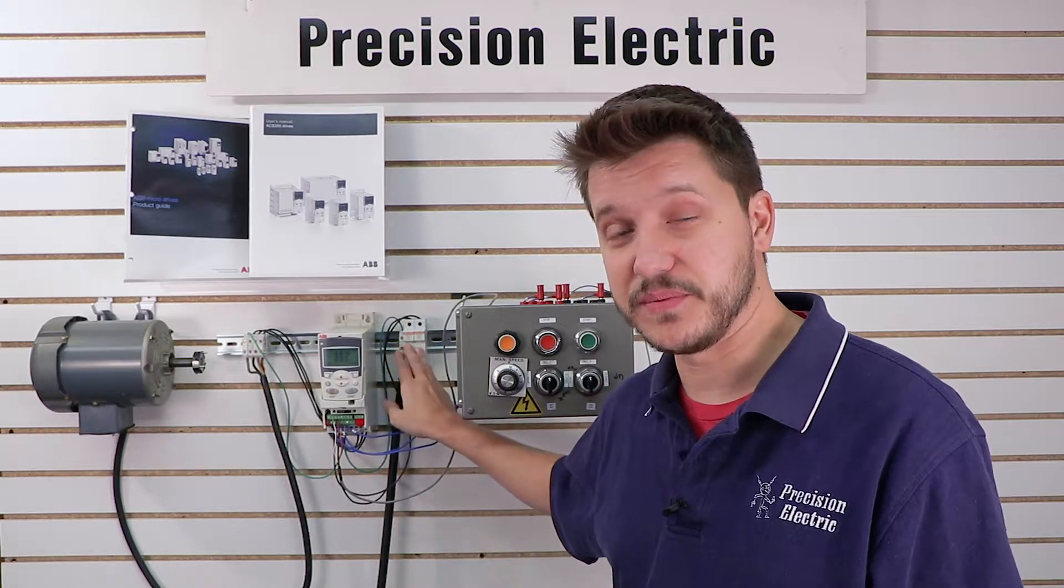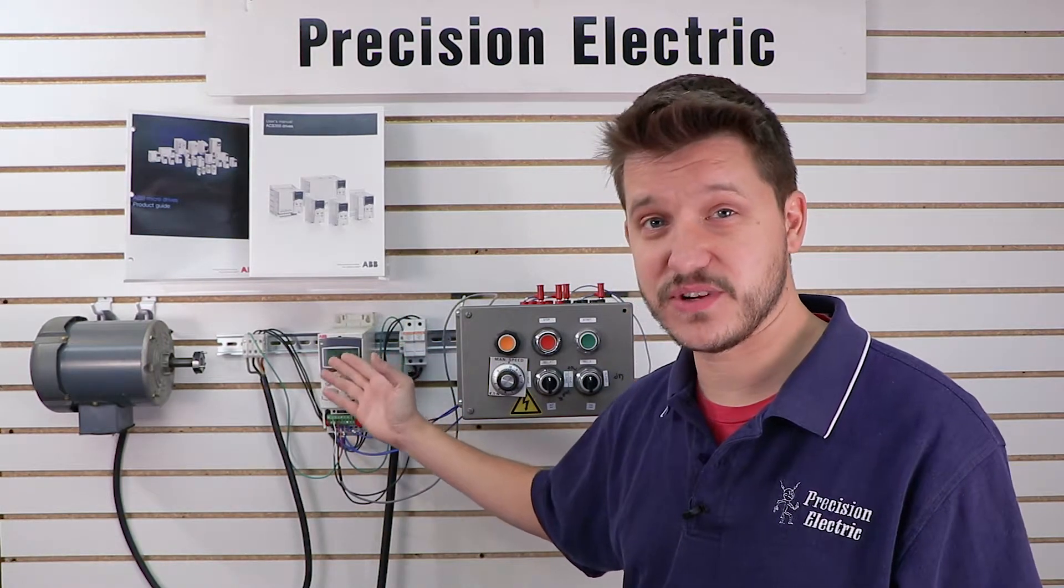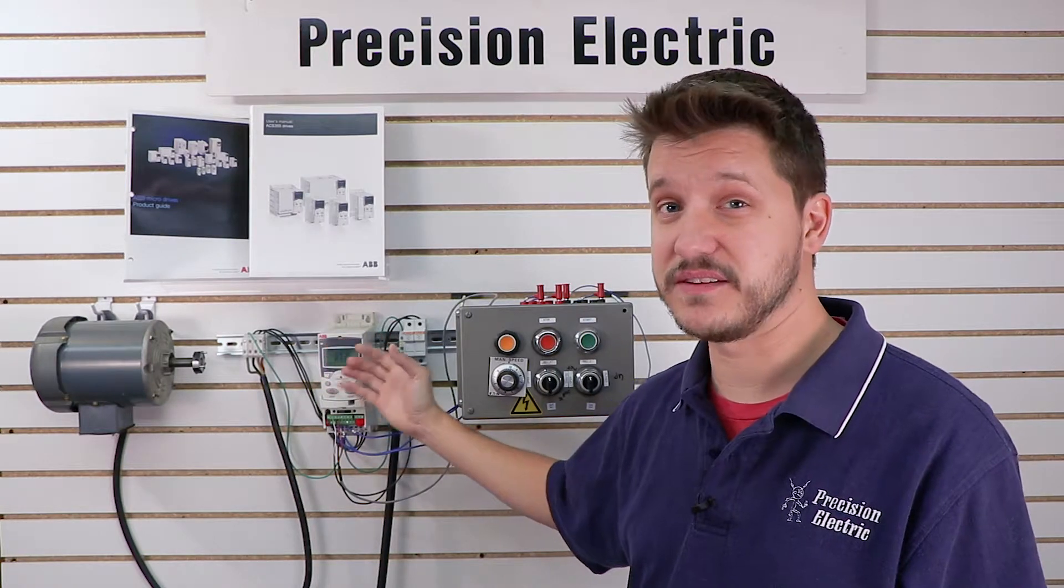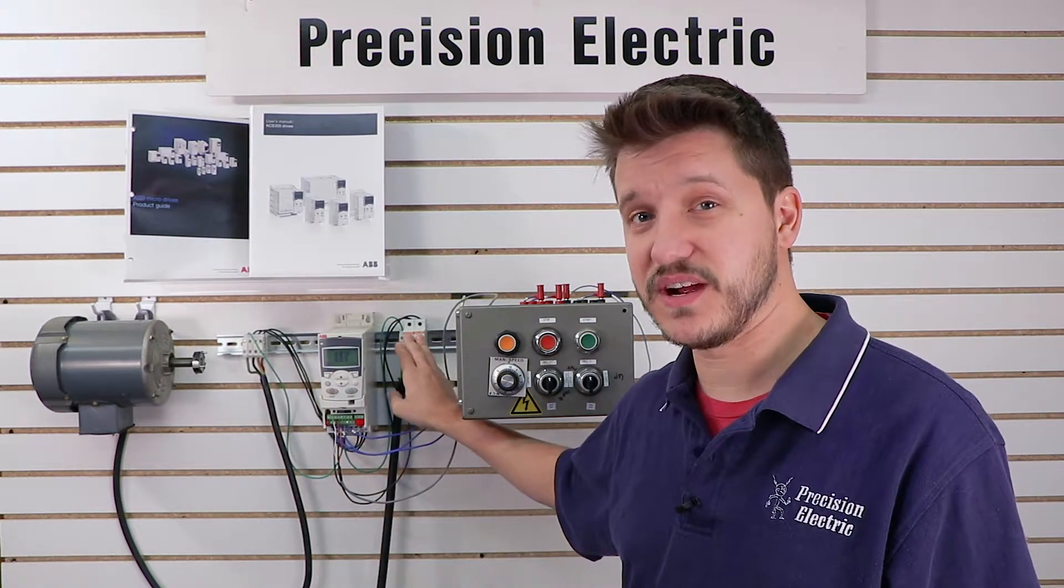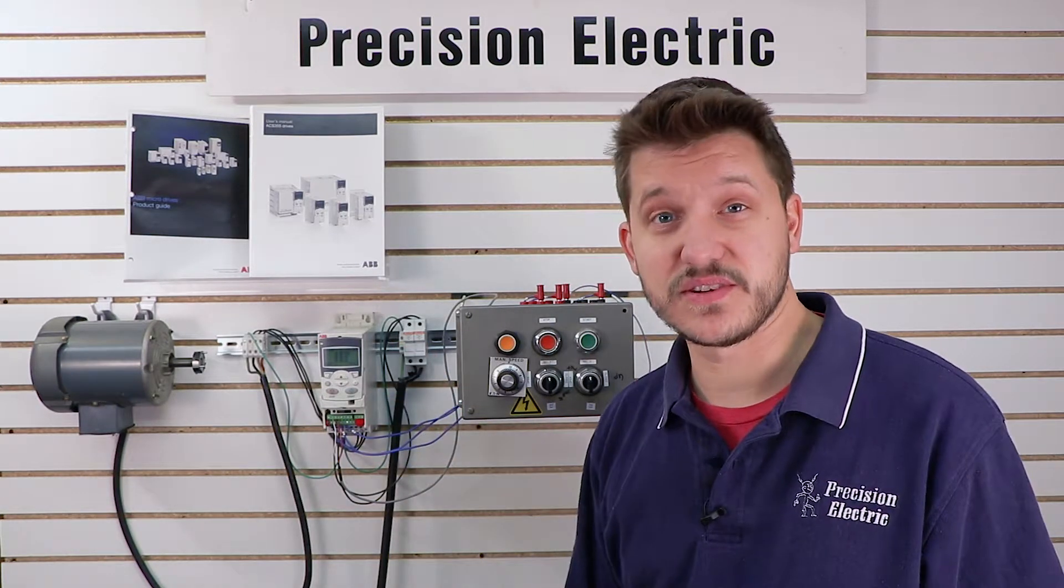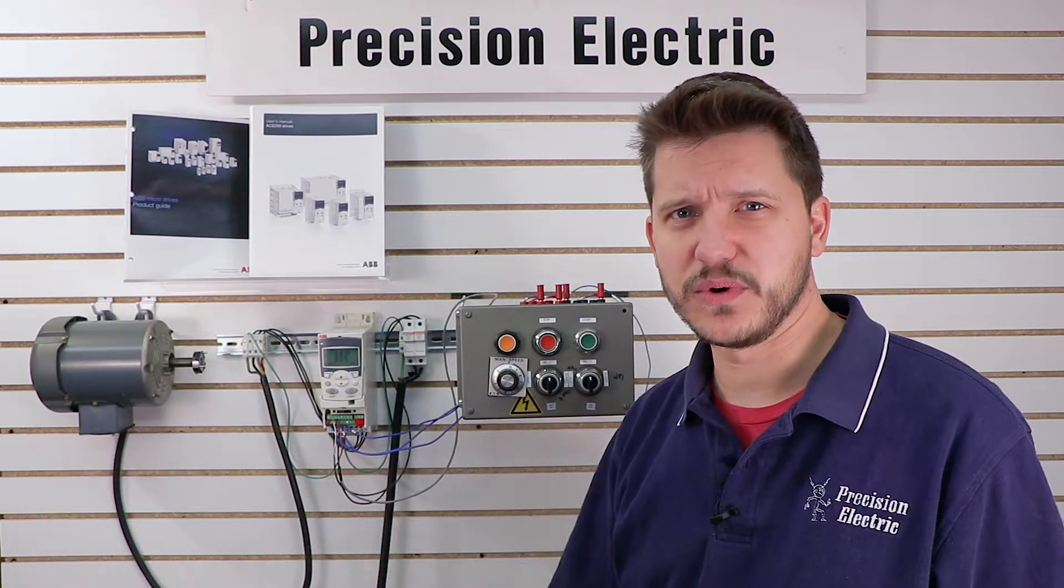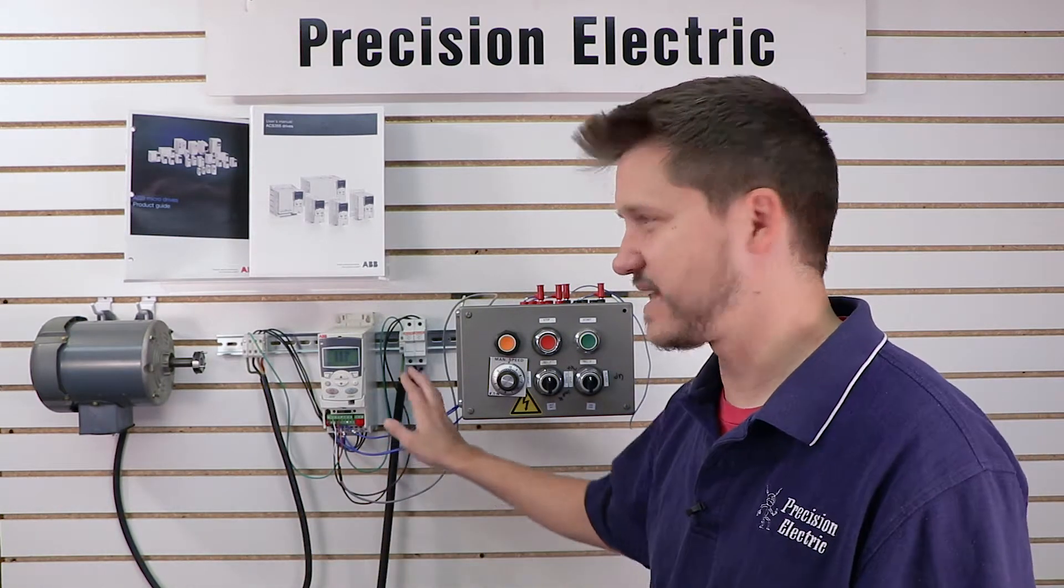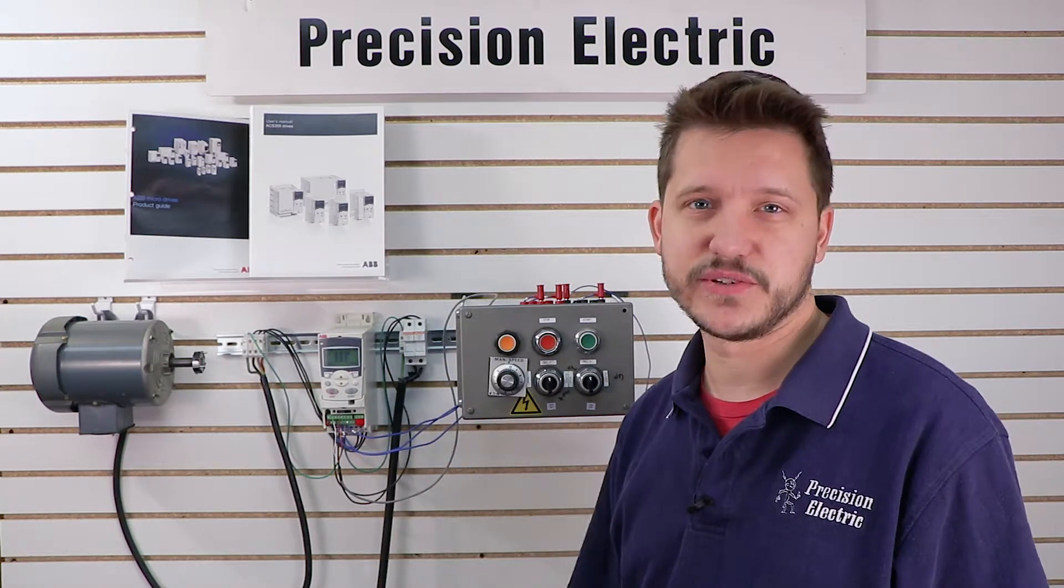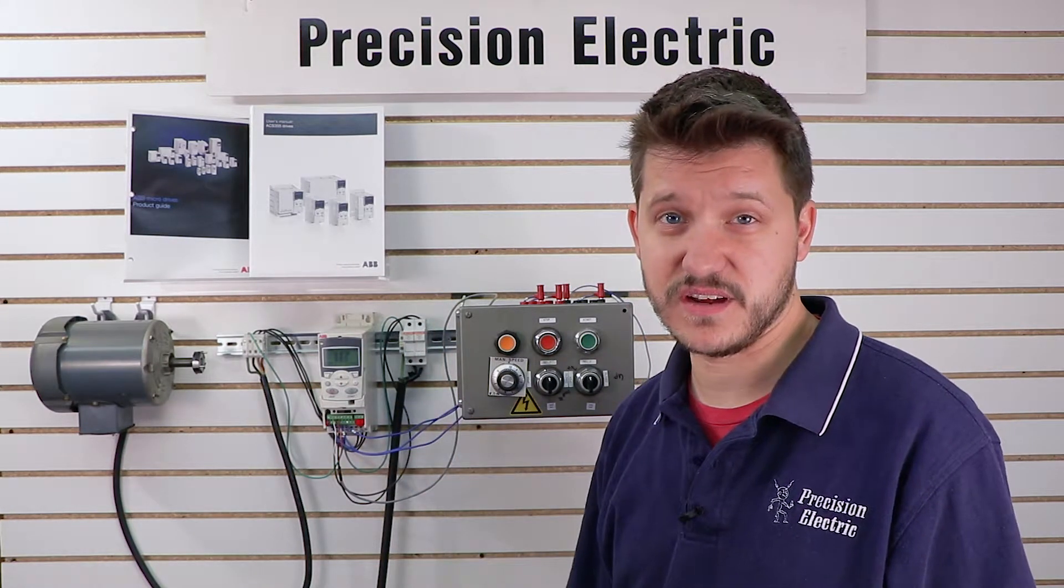We basically tell people it's cheap insurance. You buy a $500, $600 drive or maybe even a $5,000, $10,000 drive. For maybe 5% of the cost of the drive, you can protect the input section without any concerns. And it makes a huge difference. We've had a lot of customers in the field where we'll go out and find out they had a circuit breaker and it just took too long to trip. Blew up not only the breaker, but also blew up the input section of the drive.